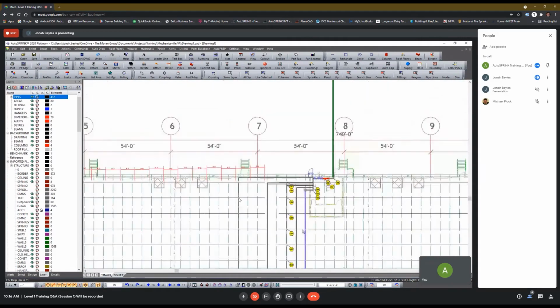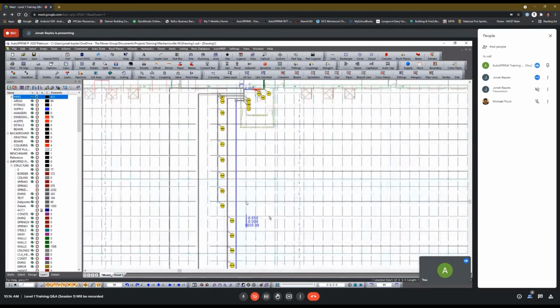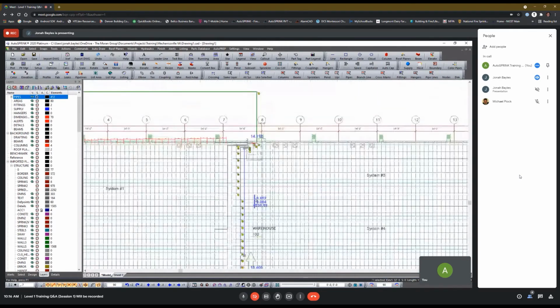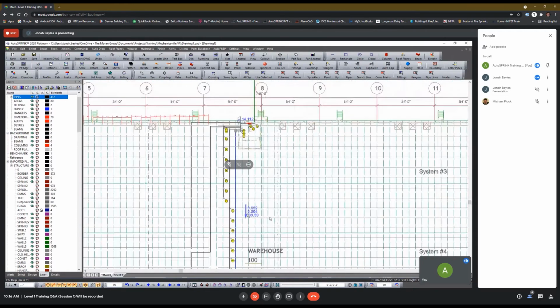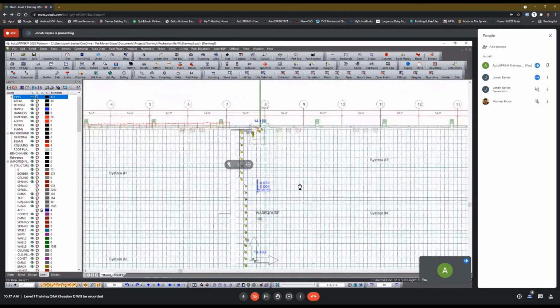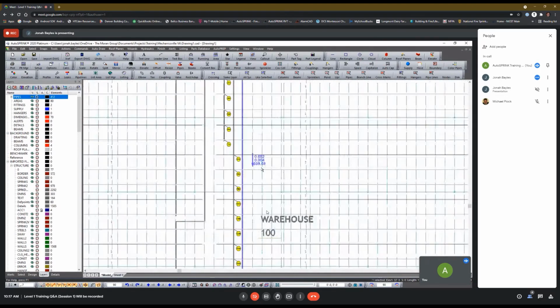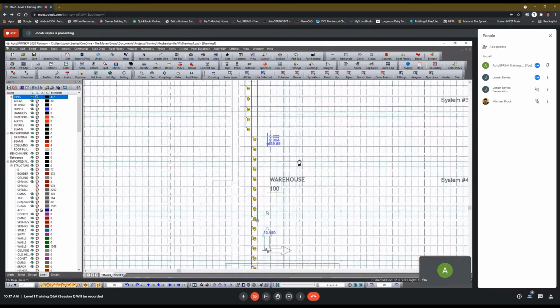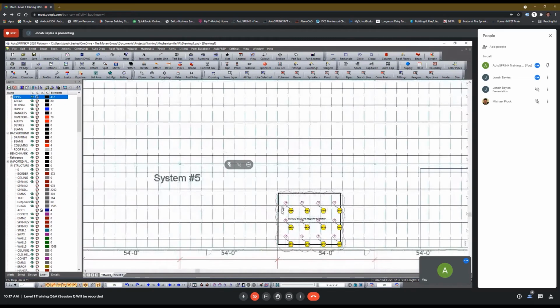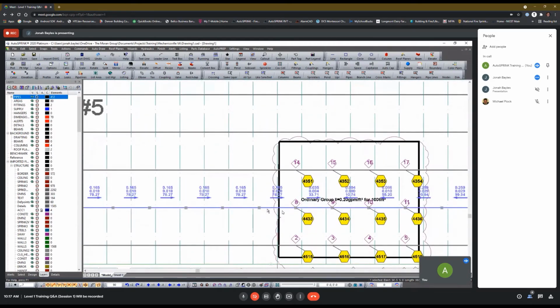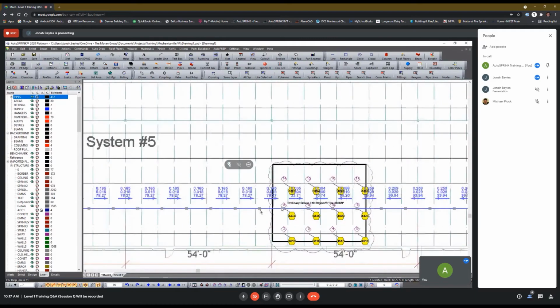I guess I just thought that was something else. No worries, man. But all these numbers seem okay. They don't seem way off, do they? The flow demand seems a little low to me, to be honest, for an ESFR system. So I certainly would recommend double checking your set minimum flow states or set minimum pressures on your sprinkler heads.